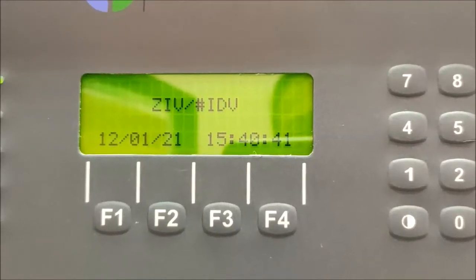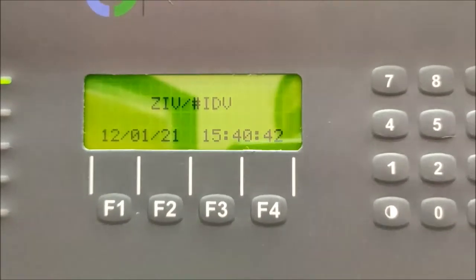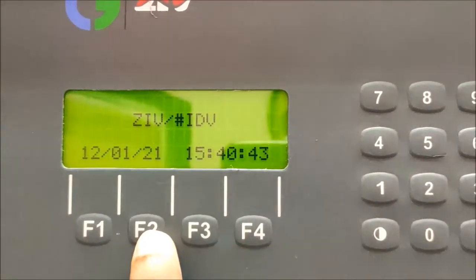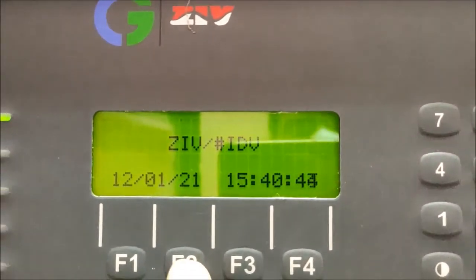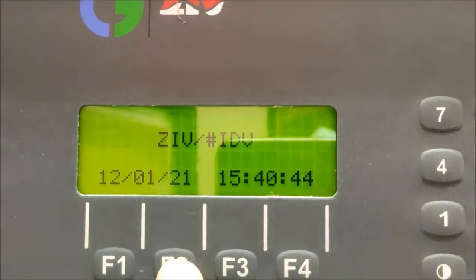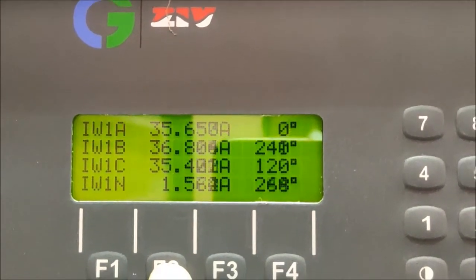To see different current in a differential relay of ZIV make, we have to first press the F2 button. If you press the F2 button, you will get the value of the HV side winding current. Here HV side winding current is represented as IW1, and A, B, C are represented as red, yellow and blue phase respectively.